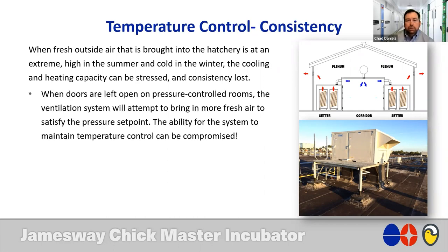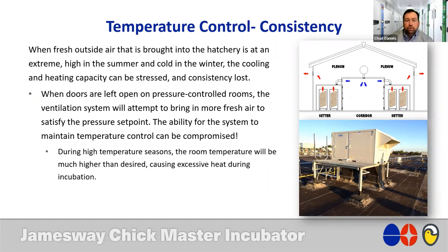One of the big things that I see on hatchery visits is when doors are left open on pressure control rooms. The ventilation system will attempt to bring in more fresh air to satisfy that pressure set point. The ability for the system to maintain temperature control is compromised. We've taken a unit like this and it's now operating at 100% fresh air. There's no return air. And if it's extreme heat outside, I'm probably not going to manage the temperature correctly. Same goes with an air handling ducted 100% fresh air supplied system. The damper is going to open up more and we're going to compromise our ability to control temperature.